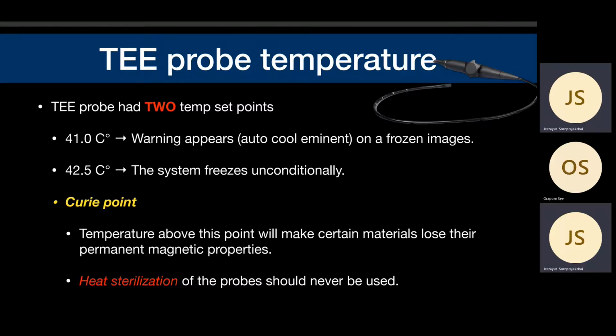And it's big too. Okay, the probe: the usual probe is temperature sensitive, because we put it in through our body, which has heat already. Some patients have IE, infective endocarditis, and we want to evaluate the stage of the IE. They already have a high fever, so the temperature will go up high. So automatically the probe header is set to a temperature of 41 degrees. When the probe reaches 41 degrees, it will warn. It has auto cooling, okay, so you will see a warning sign on the screen.